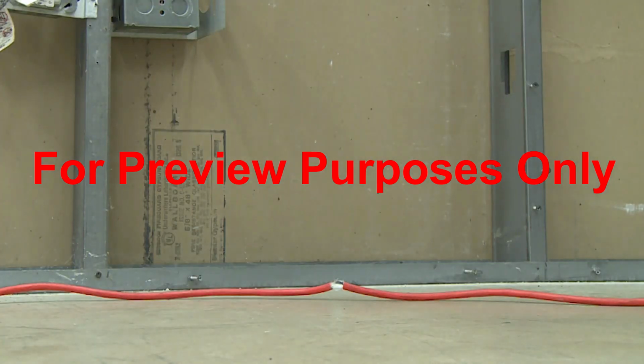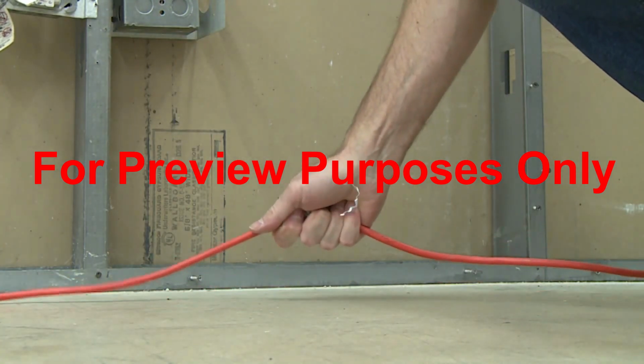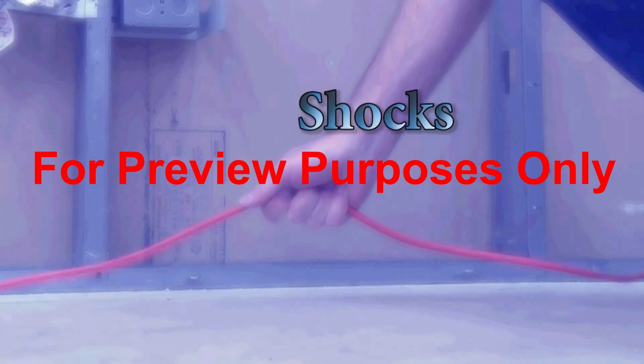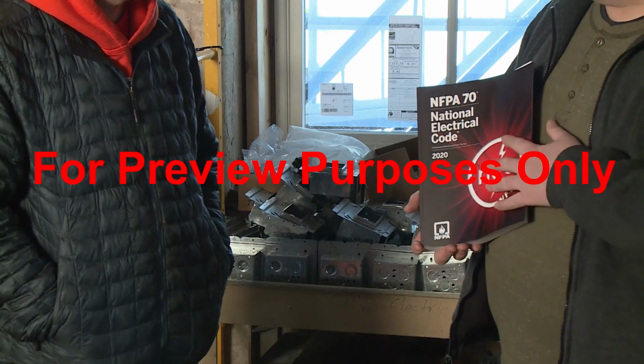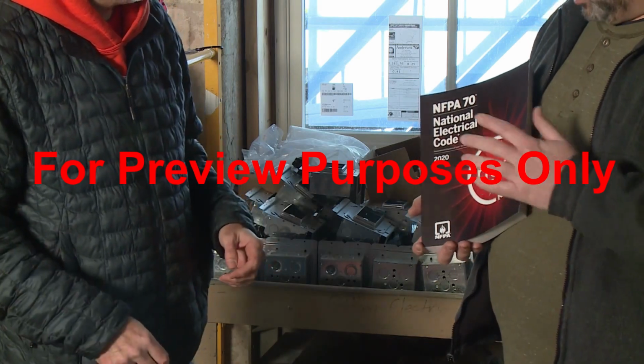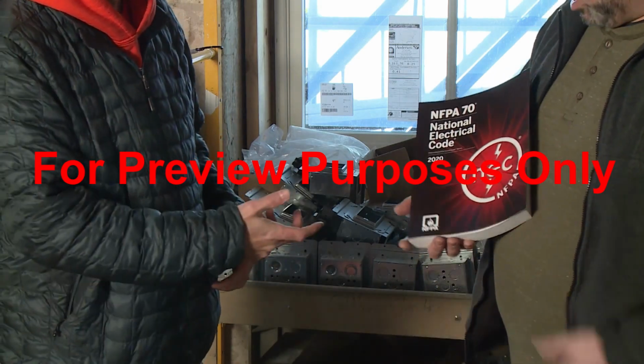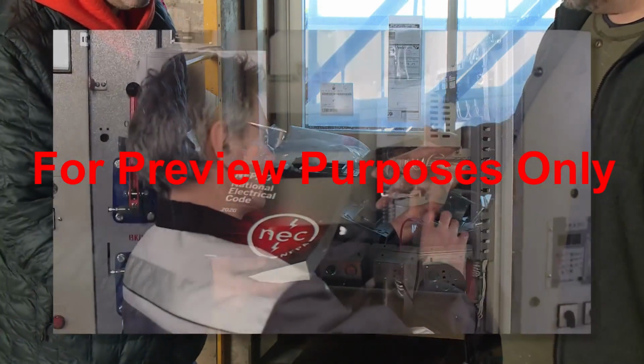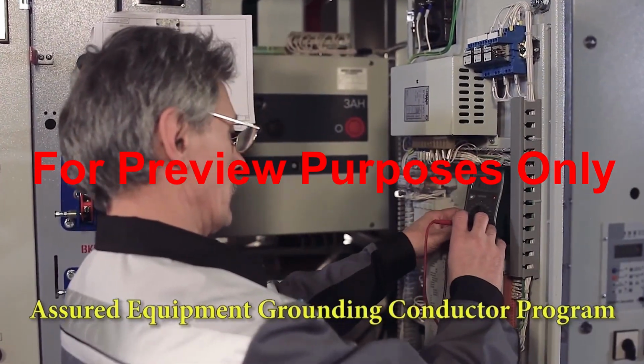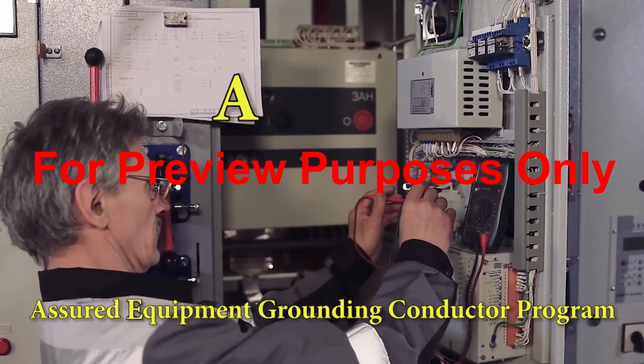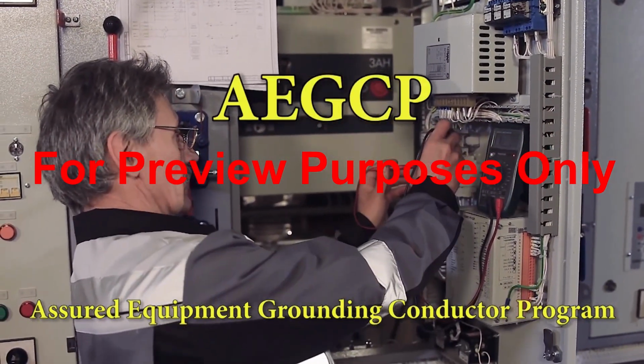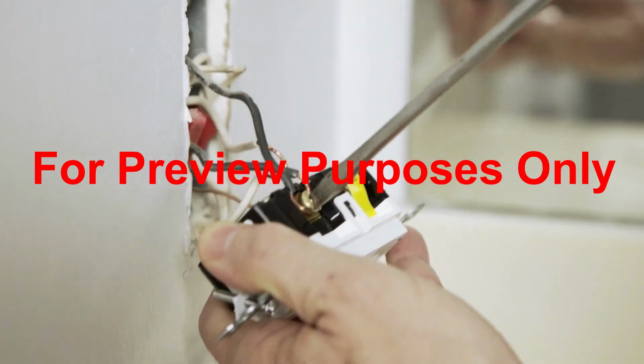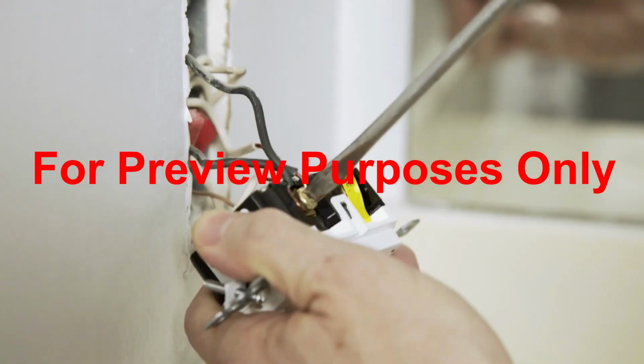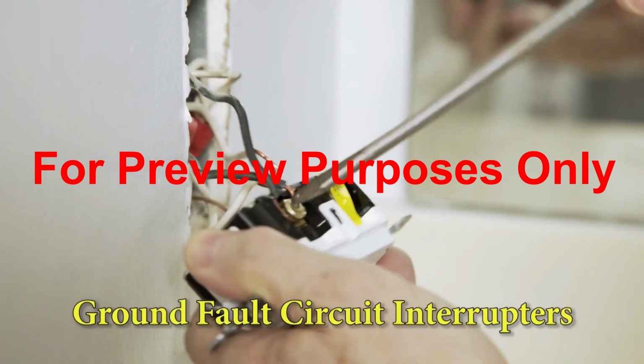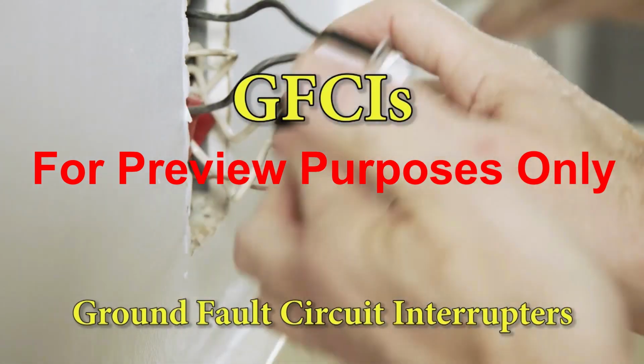If the current surges through your body on its way to the earth, ground faults can cause shocks, burns, even electrocution. To protect construction workers from these hazards, OSHA's electrical safety standards require employers to implement an Assured Equipment Grounding Conductor Program, AEGCP, on their job sites, or to equip the sites with devices called Ground Fault Circuit Interrupters, GFCIs.